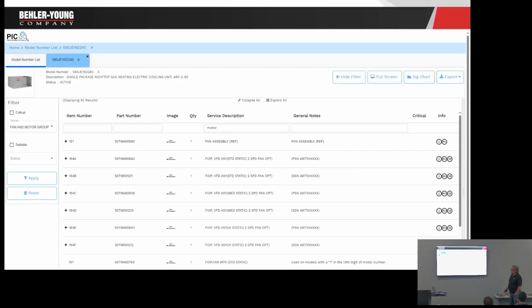It all means something. This is our parts lookup screen. Doesn't mean much to you guys. However, if I plug this in, these are all blower motors, all different VFDs, fan options for the same unit. Before 49 to 17, after 49 to 17. Single speed, 2-speed, medium static, high static, low static, standard static. So all those numbers mean something. So please get the whole number, get your camera out, take a picture of it.